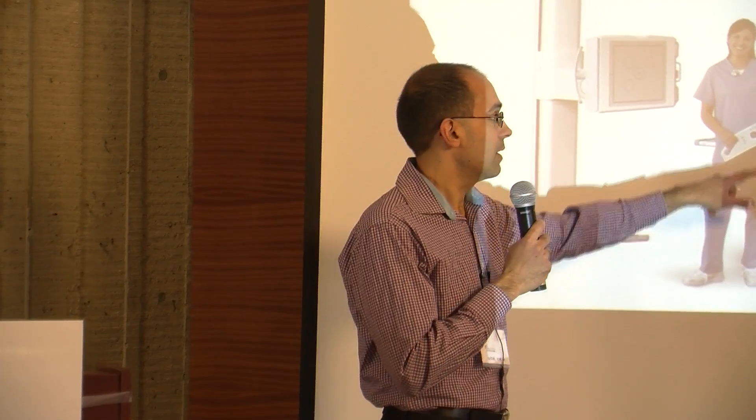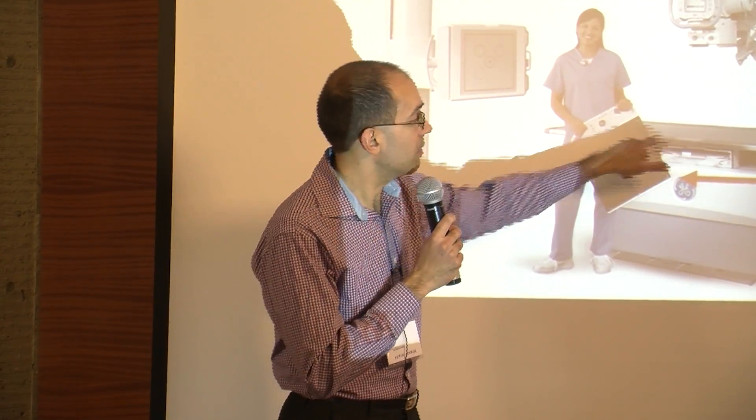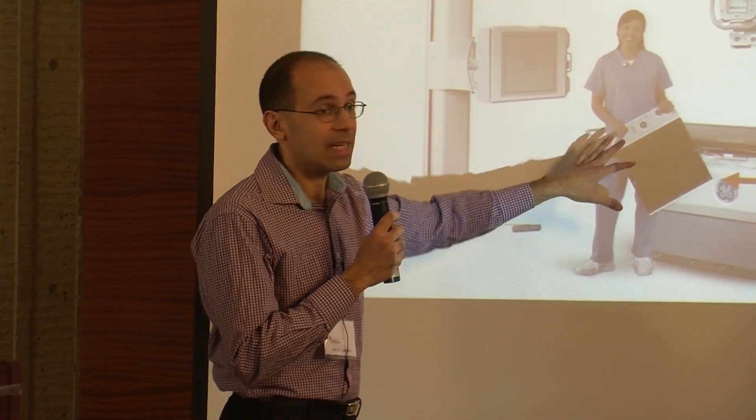What you see here is a lady holding an X-ray detector, the device that actually captures the X-rays. There's the X-ray source, the X-ray table, the patient lies there, and this X-ray camera slides in underneath. This device has replaced X-ray film. X-ray film had to be large because you can't focus X-rays — it has to be as large as the object being imaged, whether that's the chest, leg, or whatever. X-rays finally went digital around the year 2000, just like film cameras transitioned into digital cameras.